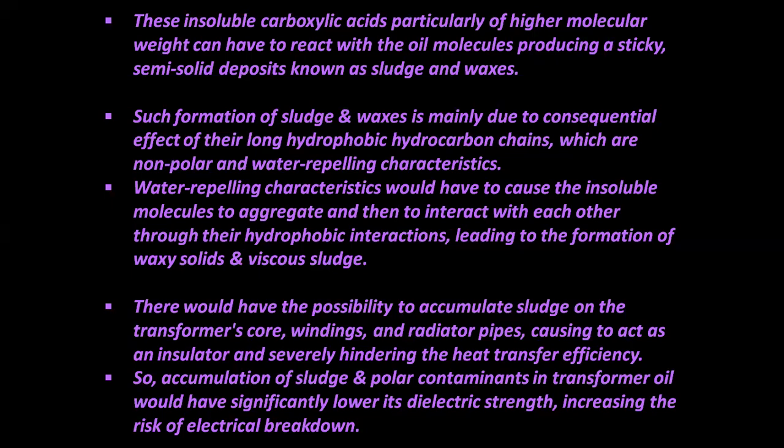There is the possibility of sludge accumulating on the transformer's core, windings, and radiator pipes, acting as an insulator and severely hindering the heat transfer efficiency. So, accumulation of sludge and polar contaminants in transformer oil would significantly lower its dielectric strength, increasing the risk of electrical breakdown.